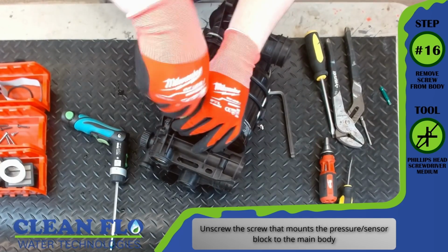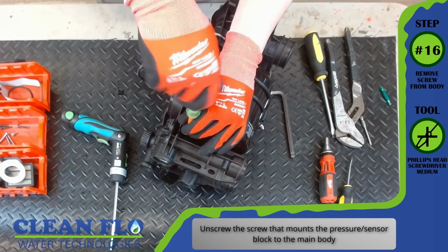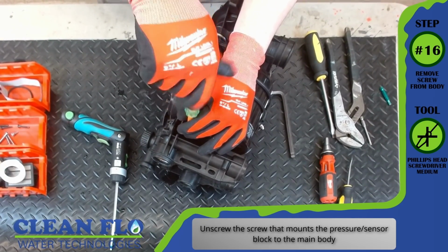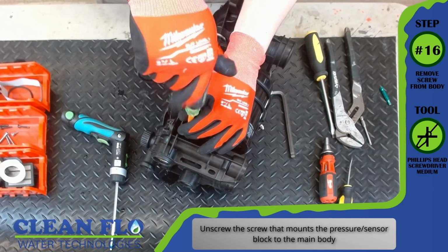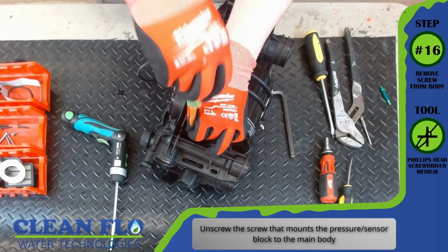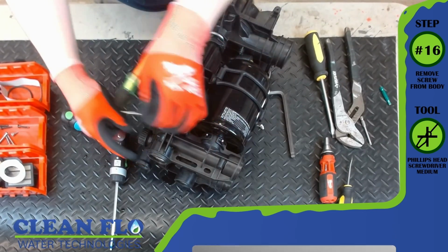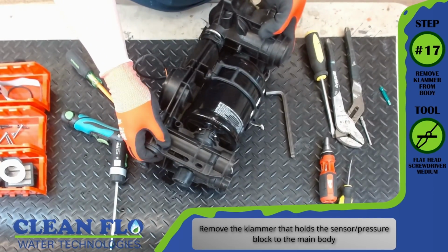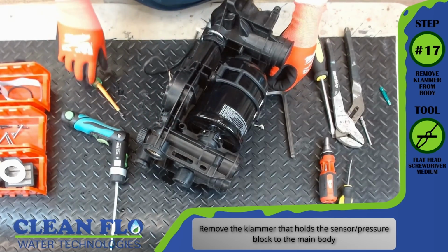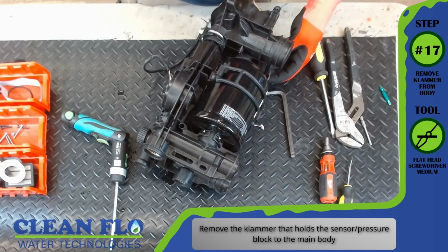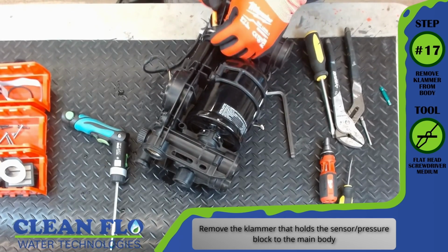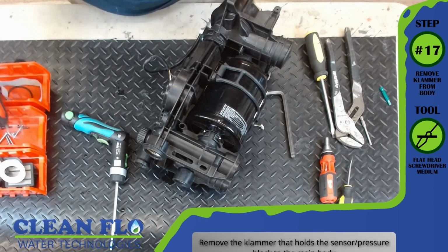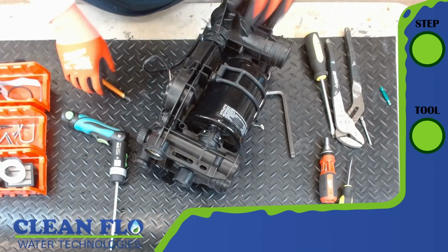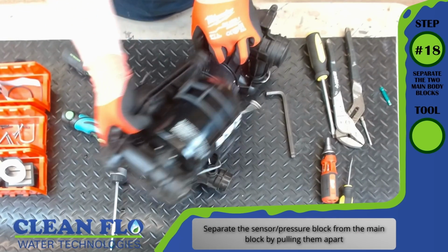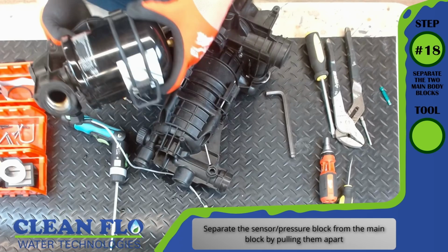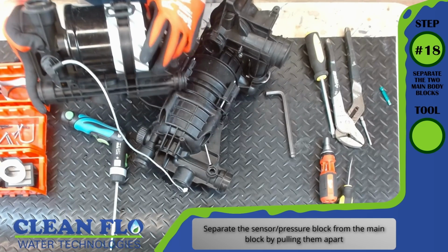Step 16, remove the screw from the body. Tool, Phillips head screwdriver, medium. Unscrew the screw that mounts the pressure sensor block to the main body. Step 17, remove clamp from body. Tool, flathead screwdriver. Remove the clamp that holds the sensor pressure block to the main body. Step 18, separate the 2 main body blocks. Separate the sensor block from the main body block by pulling them apart.